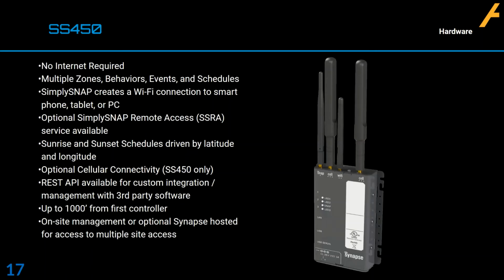The basis of our system is a head-end gateway, which can be installed inside a building—we often put them in server rooms or electrical rooms. We also have the ability to put it into a NEMA-rated box for customers who can't install it indoors, so it can be mounted on the exterior of a building or somewhere remote. The main limitation is that we typically like to be within 1,000 feet of the first controller before we start talking to the mesh network, so we only need to talk to one controller before the whole system starts communicating together.